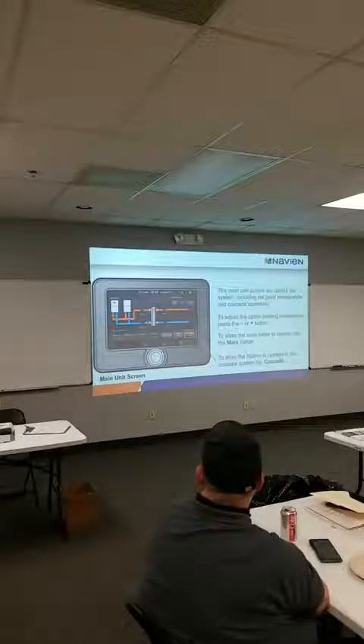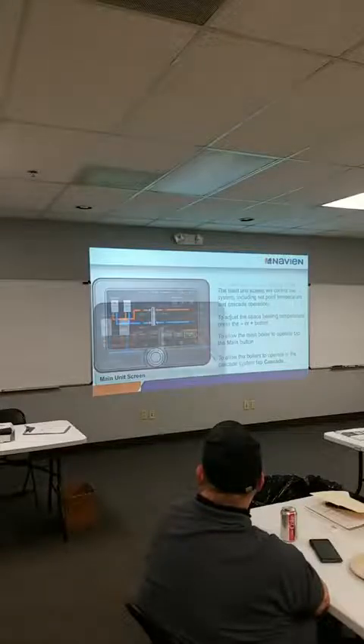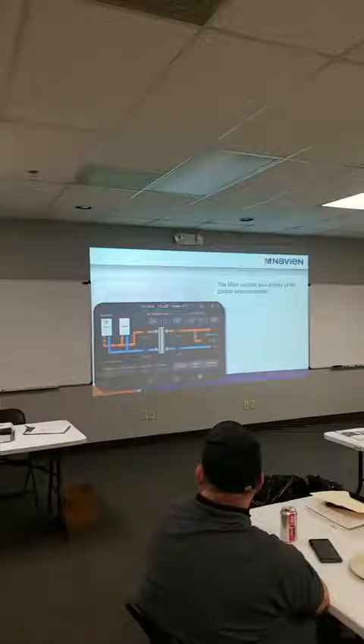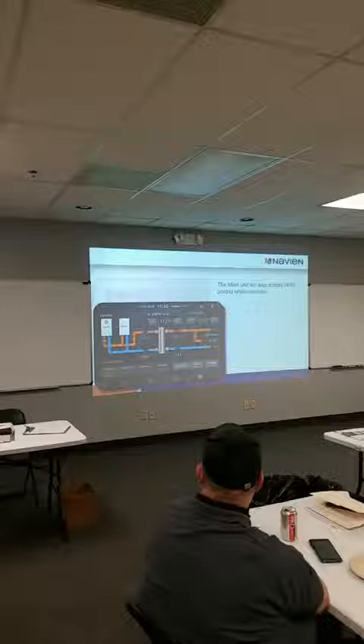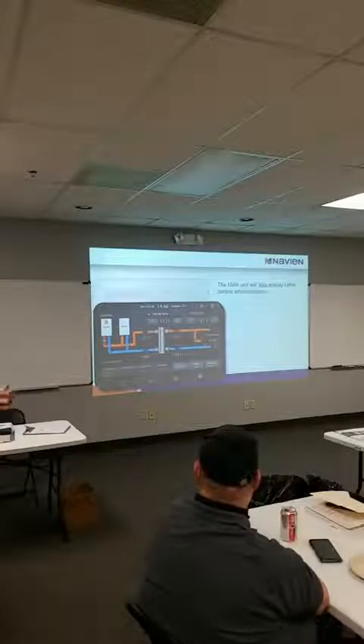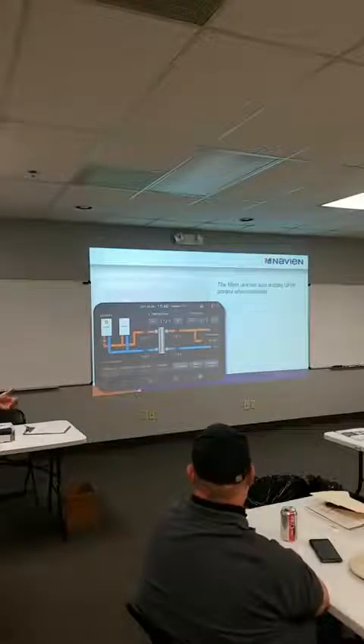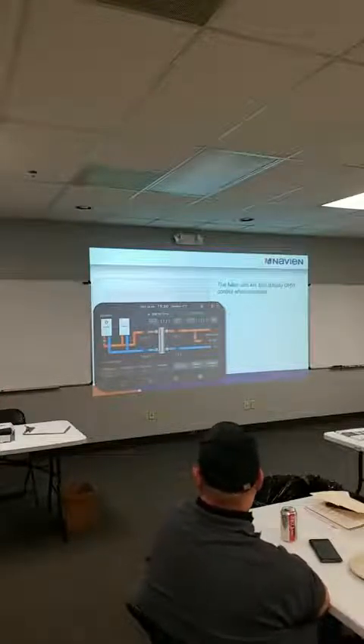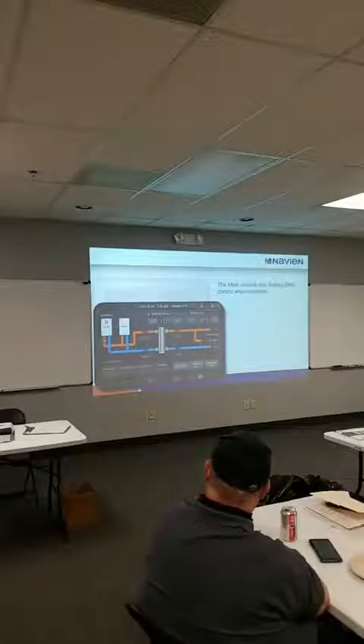Right there, you got a main button and a cascade button. You can change how the system's running. I think there's way too much here, but any information you could possibly want is stored here. You can find it very simple. Again, you don't need our manuals to program the boiler. You could just run this thing on. You can set supply temperature and let it run off defaults. If something's not working properly, you go back in and change some of our default settings if you need to. Or you can set it up based on how you like to run stuff.